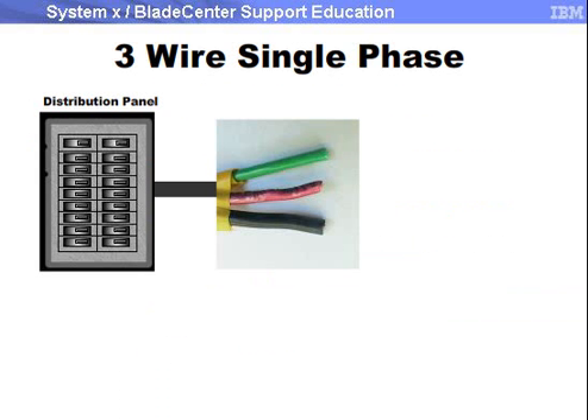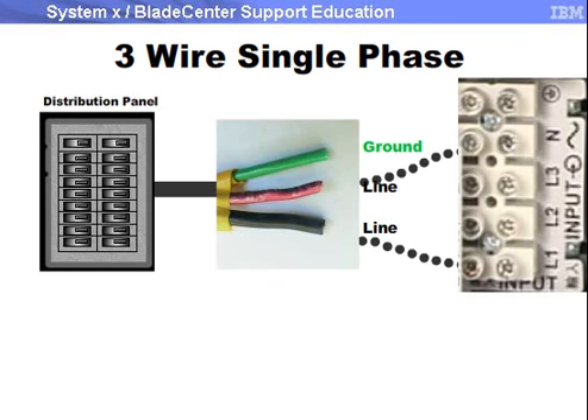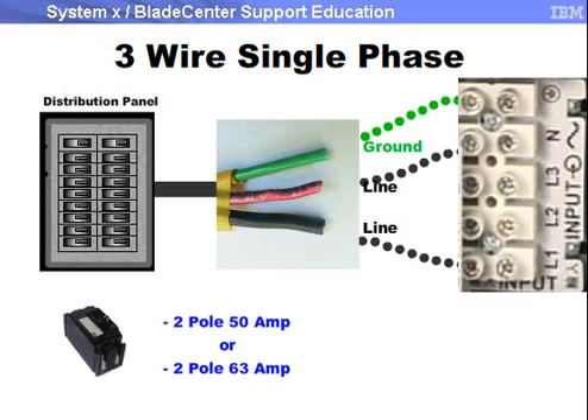3-wire single-phase wiring connects the two supply wires and ground wire from the distribution panel to the L1, L2, and ground inputs, respectively, of the UPS input terminal block. The external circuit breaker in the distribution panel will typically be a 2-pole 50 amp or a 2-pole 63 amp breaker, depending on the UPS output rating and the local electrical codes in force.